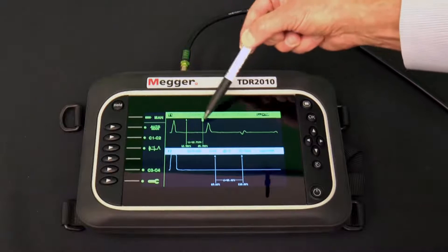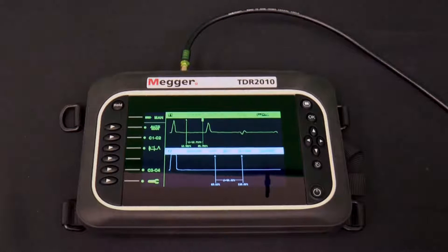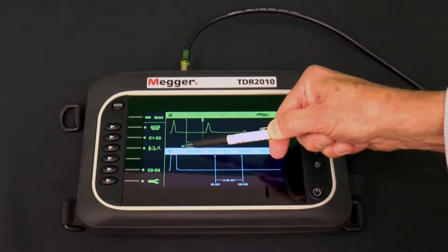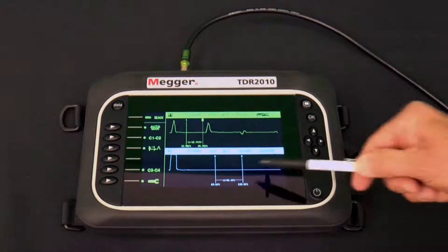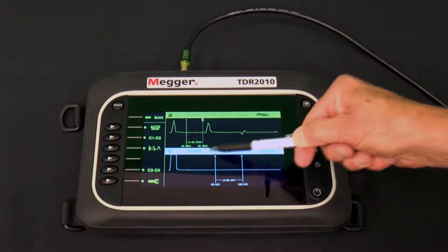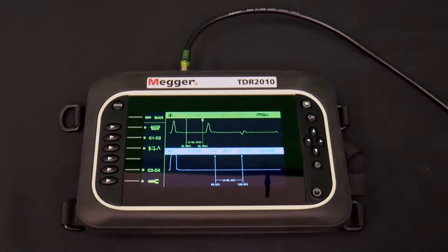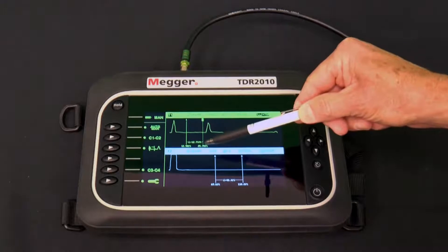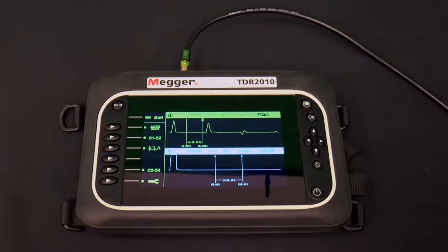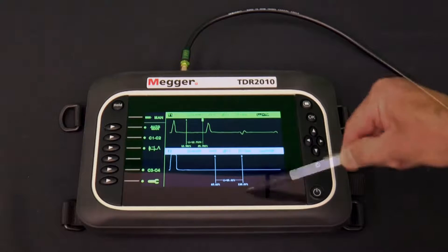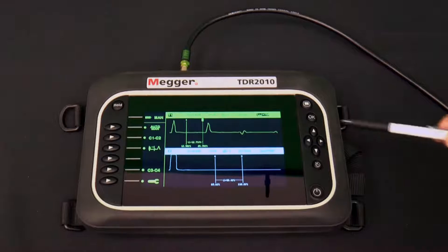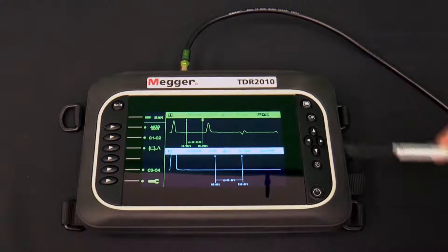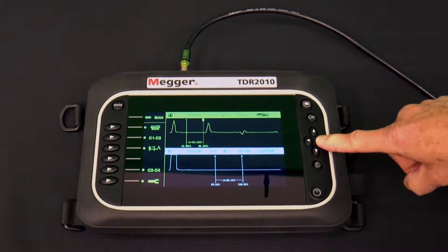Each trace has two cursors. The distance from the TDR2010 to each cursor is at the bottom of the screen under that cursor. The distance between the cursors is right next to the delta sign, the triangle. In this case, there are four cursors on the screen. The active one — the one that is controlled by the left and right arrows of the navigation group — is a dashed line. The other three are solid lines.